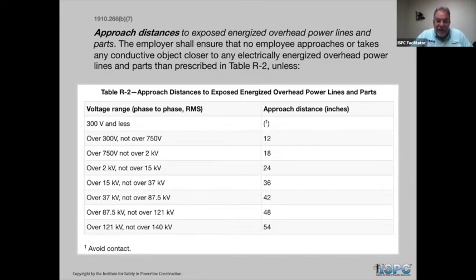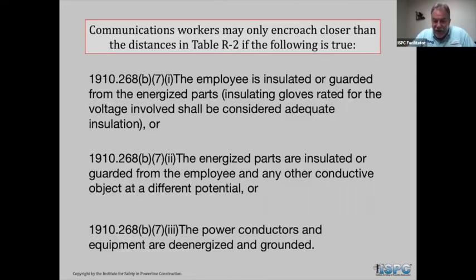Now, the question I usually get here is, all right, Tony, you're saying 2 feet. Is that the energized conductor? Well, the neutral is a current carrying grounded conductor, hopefully grounded. If you hadn't had any copper thieves in a while, maybe it might be grounded very well. So do I have to be 24 inches from that system neutral? OSHA says, yes, you do.